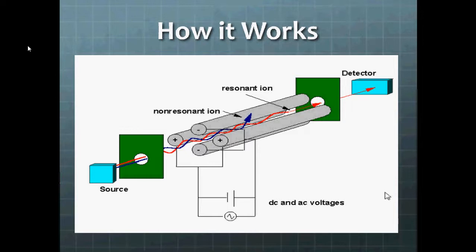For every voltage that is scanned through, there's a specific and small range of mass to charge ratio that will be able to make it through the quadrupole at that particular voltage. These are called your resonant ions. Now the rest of the ions will veer off and collide with the rods and lose their charge, become neutral, and then they will eventually be sucked out by the vacuum pump.